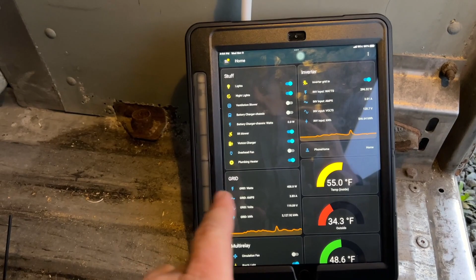So what we want to look at here is right now we've got about 400 watts pulling on the entire grid, and then this is our inverter grid cutoff here. So we want to watch that number, and then that switch should automatically toggle. So I'm going to activate this heater, and let's see what our numbers jump up to and see if this actually works. There we go.